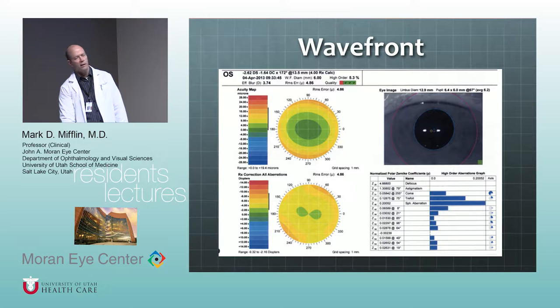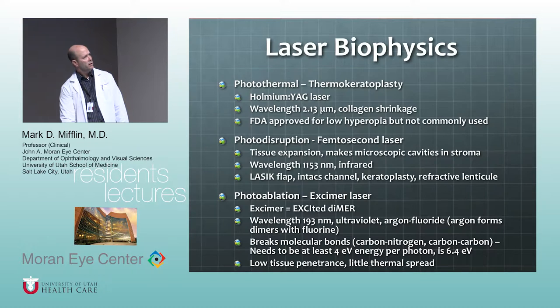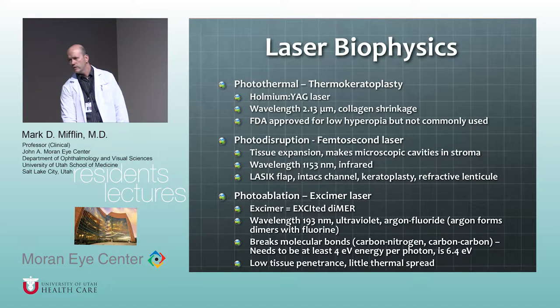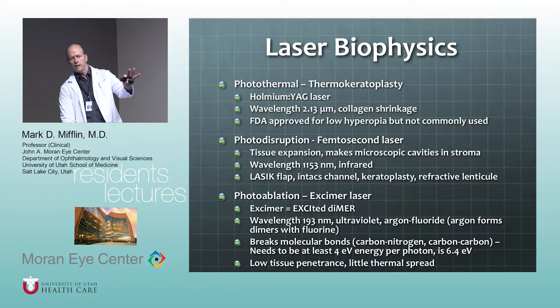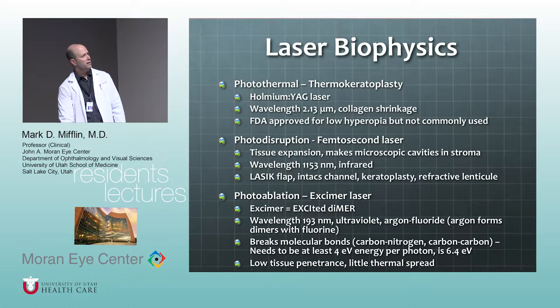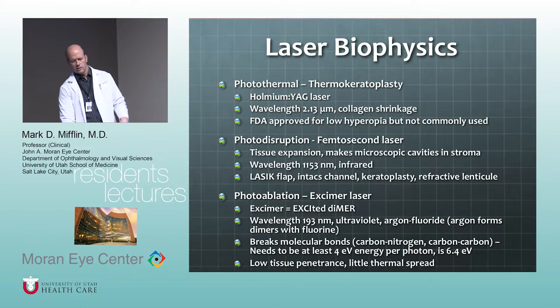Wavefront uses an optical computerized data set collected by a machine called an aberrometer. An aberrometer is a scanner — it shines low-energy, infrared-spectrum collimated light into the eye, which is then reflected out and collected on a sensor. There are a couple of different ways of aberrometry; the most common is Hartmann-Shack, which is what I just described.